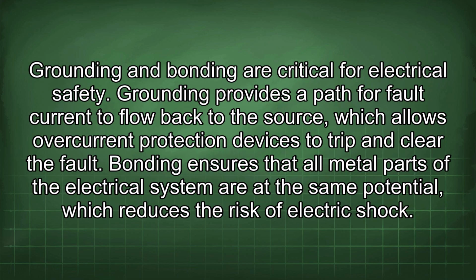Grounding and bonding are critical for electrical safety. Grounding provides a path for fault current to flow back to the source, which allows overcurrent protection devices to trip and clear the fault. Bonding ensures that all metal parts of the electrical system are at the same potential, which reduces the risk of electric shock.